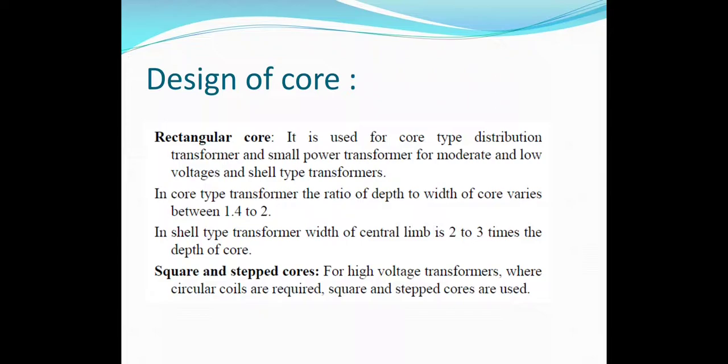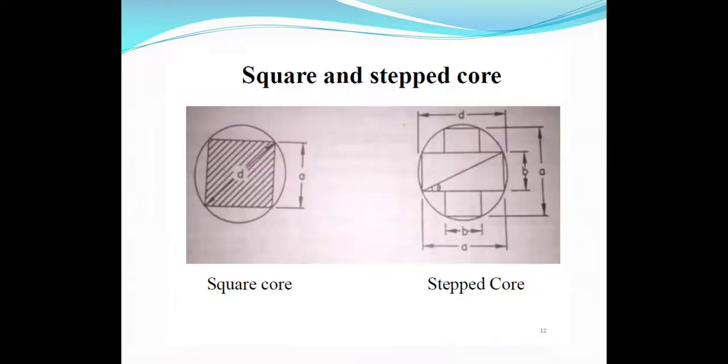If we use circular coils, the forces will act tangentially. As a result, deformation of the coil or winding will not occur. So the main reason to choose a circular coil is to avoid deformation of the coil when the current value exceeds a certain level.